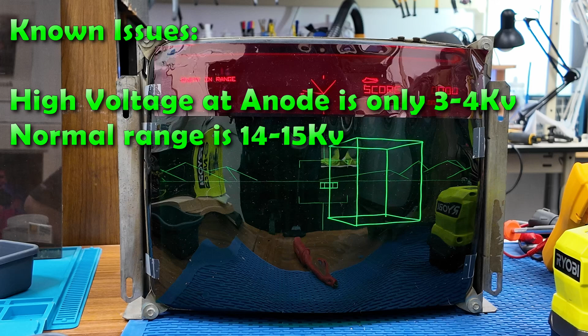The obvious problem that we have right now is that the high voltage at the anode clip is only 3 to 4K. That should be in the 14 to 15K volts range, so it's significantly lower than it should be. I think the most likely cause is either the high voltage transformer or the high voltage rectifier diode is not working properly.